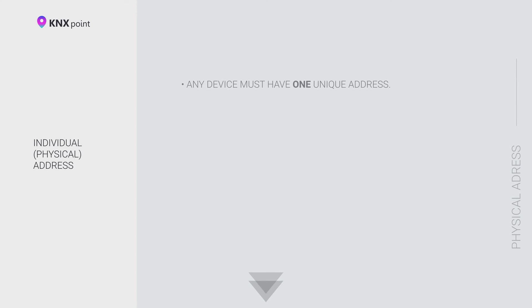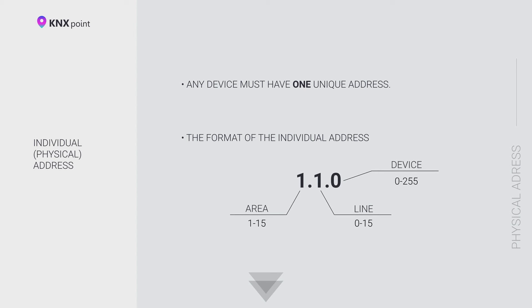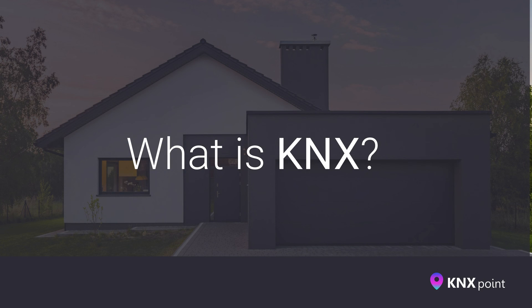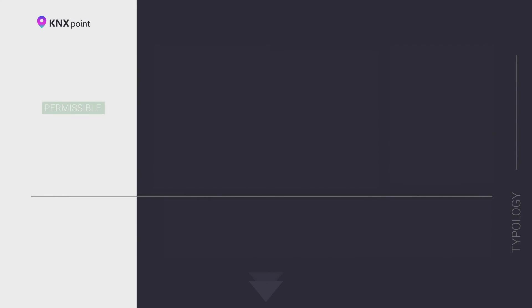Each KNX device has its own individual physical address on the bus. The KNX device address corresponds to the position of the device in the topology of the entire installation. This is the first parameter that should be assigned to the device. The physical address of a KNX device has the following format: number of the area to which the device belongs, number of the line or line segment on which the KNX device is located, and device number. There can be up to 57,600 devices in one KNX installation. Primarily, the physical individual address is used to set up and commission the system.